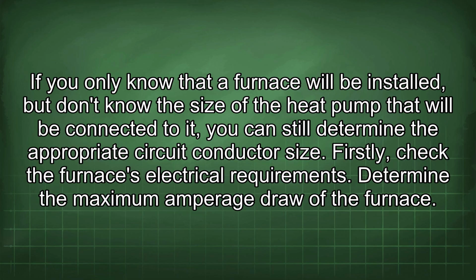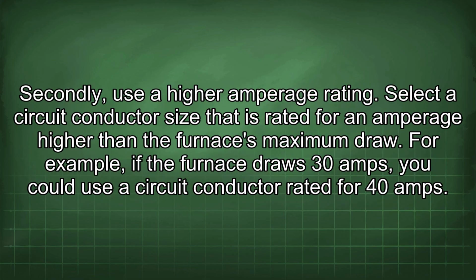If you only know that a furnace will be installed but don't know the size of the heat pump that will be connected to it, you can still determine the appropriate circuit conductor size. Firstly, check the furnace's electrical requirements. Determine the maximum amperage draw of the furnace. Secondly, use a higher amperage rating. Select a circuit conductor size that is rated for an amperage higher than the furnace's maximum draw. For example, if the furnace draws 30 amps, you could use a circuit conductor rated for 40 amps.